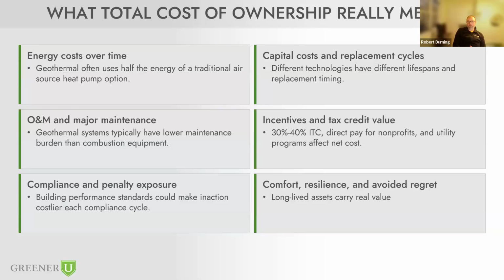A geothermal system can be 2 to 3 times as efficient as an air source system. How long are these pieces of equipment going to last? A geothermal loop underground could last 50 to 100 years. These are well-designed systems, undisturbed. They're going to last. You're also moving maybe outdoor compressors for air source systems into a water source heat pump that's going to sit in a basement. A compressor and a fan outside is going to have a lot shorter life cycle than a moving piece of equipment down in a basement.